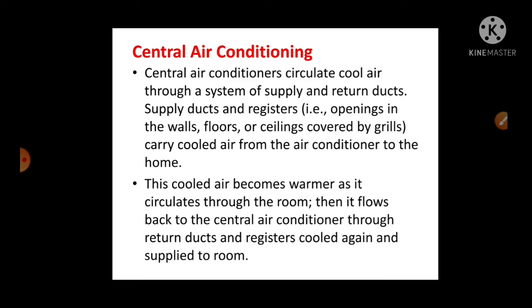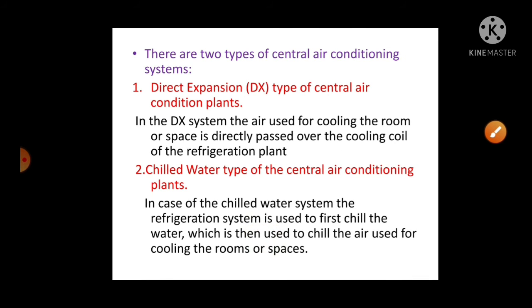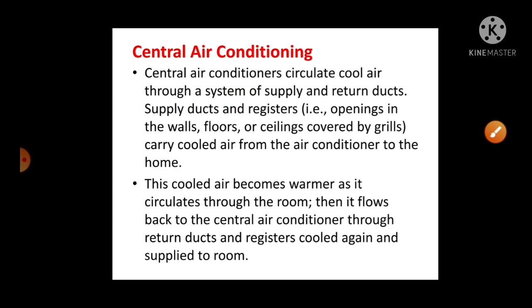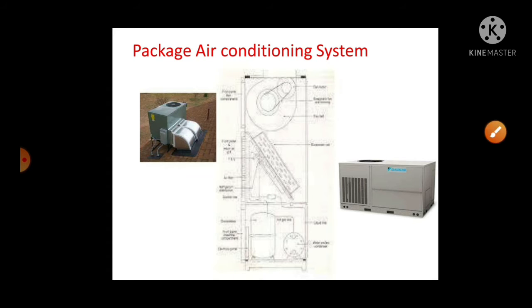Here, a water cooled condenser is used. This is a compressor, where hermetically sealed compressors and condensers are located in the cabinet. This is a packed unit which is located at the bottom. So the compressed high pressure vapors are passed to the condenser, where water cooled shell and tube condensers are used.